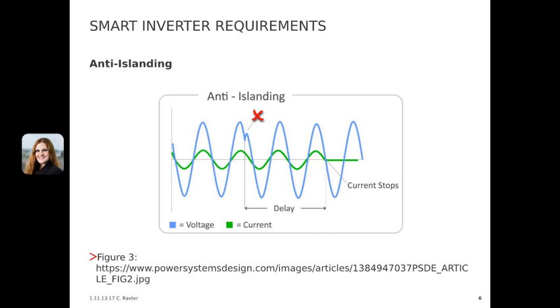Because of this, DER inverters have the intelligence to disconnect in the event of abnormal conditions at the site where they are installed. DERs alone cannot operate without a voltage source and disconnect according to the utility requirements to prevent an islanding event.